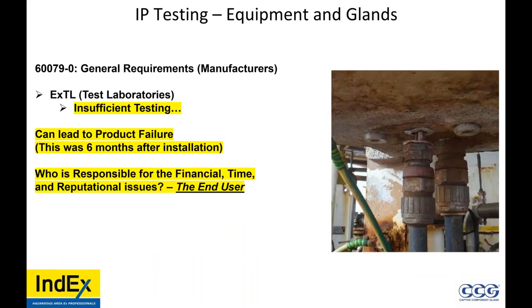Now, insufficient testing can lead to product failure. This was 6 months after installation. The IP washer failed. Water got in and caused corrosion. So who is responsible for the financial, the time, and the reputational issues of this happening? The end user. So if the manufacturer sold them a cheap gland, or the EPC purchased a cheap gland without considering the environmental conditions, well, the end user, the likes of major oil and gas companies, now it's their responsibility. It's not good. So you see the issues, yes? Everything goes to the end user.